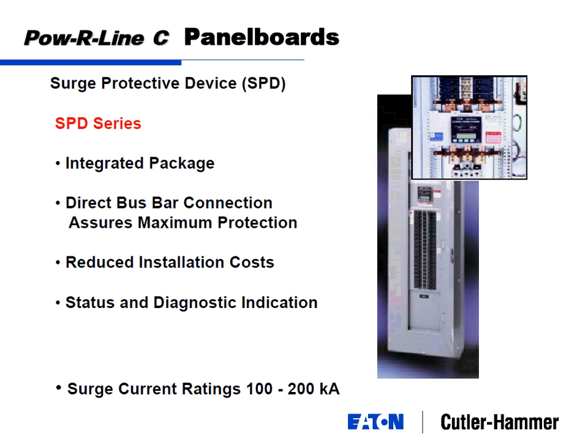What the SPD does is it absorbs the transient overvoltage and shunts the extra energy to ground. So, a real world example: there are two ways that transient overvoltages occur. One is coming from outside the building. Think about a lightning strike on the roof of your neighbor or on the power lines running down the street. If lightning hits that, it's going to travel down the conductors pretty quickly. I mean, that's a great current carrying path for lightning. So it's going to follow those conductors, and odds are something's going to hit your facility.